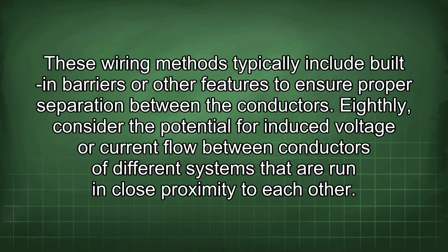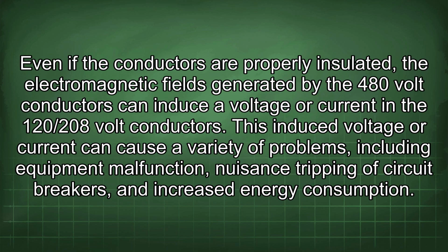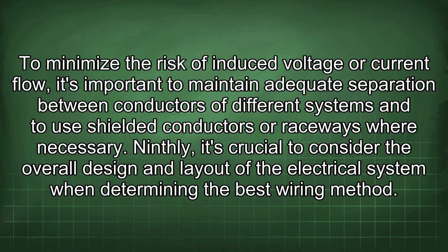Eighthly, consider the potential for induced voltage or current flow between conductors of different systems that are run in close proximity to each other. Even if the conductors are properly insulated, the electromagnetic fields generated by the 480-volt conductors can induce a voltage or current in the 120/208-volt conductors. This induced voltage or current can cause a variety of problems, including equipment malfunction, nuisance tripping of circuit breakers, and increased energy consumption. To minimize the risk of induced voltage or current flow, it's important to maintain adequate separation between conductors of different systems and to use shielded conductors or raceways where necessary.